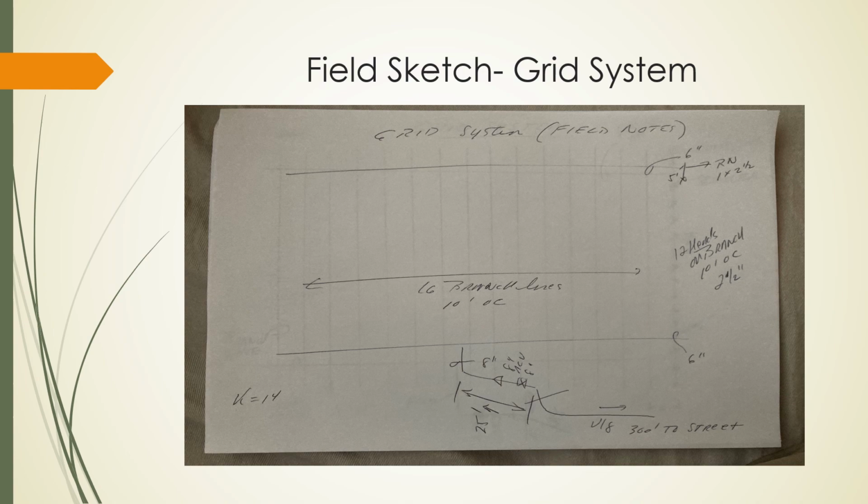Now, if you recall on our sketch outside, as I said on the loop, I have to sketch the entire branch line. On this thing, I didn't even bother including the heads that were outside the near and far main. Those are called outriggers. So if there are like 2 heads that are outside the near and far branch line, then I'm not going to include them in the sketch of the calculations. They're probably not going to be germane to the situation.